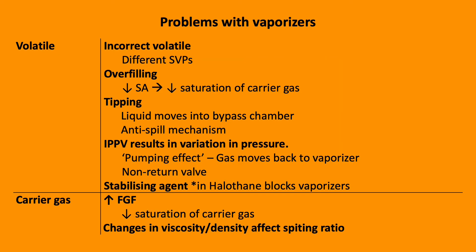Problems with vaporizers — this is not an exhaustive list. Issues include: incorrect volatile in a vaporizer; overfilling, which reduces surface area and therefore reduces saturation of the carrier gas; tipping of the vaporizer, which may cause liquid to move into the bypass chamber increasing output — reduced by an anti-spill mechanism; IPPV causing pressure variation and gas moving back into the vaporizer, known as the pumping effect — reduced by a non-return valve; halothane contains a stabilizing agent which can block vaporizers; and high fresh gas flow levels may reduce saturation. Changes in viscosity and density of the carrier gas may also affect splitting ratios.